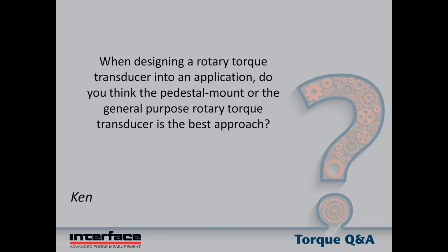Next question. When designing a rotary torque transducer into an application, do you think the pedestal mount or the general purpose, I'd say floating mount torque transducer is the best approach? I typically start with a floating mount. Basically, the sensor should always be protected by appropriate couplings. On a pedestal or a foot mount application, there need to be double flex couplings at each end of the sensor. The sensor is never intended to be used as a bearing block.